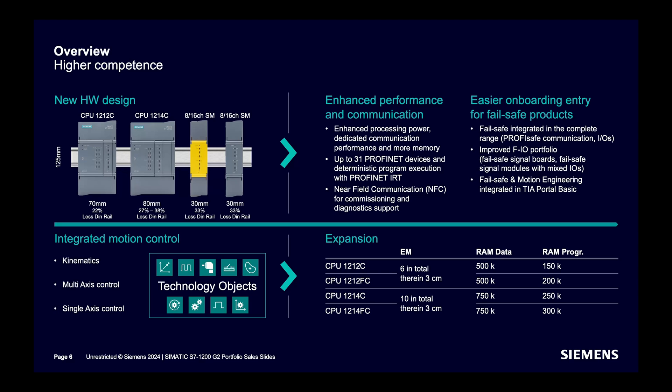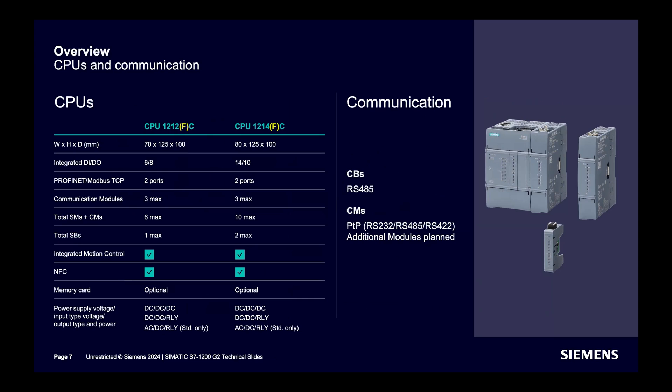This is the overview of the new CPU-1212 and CPU-1214. Width has been reduced and height has been increased. Integrated DI and DO is 6 and 8 for CPU-1212, and 14 and 10 for CPU-1214. Two PROFINET or MODBUS ports are now available. Three communication modules are supported for both. Six signal boards and signal modules are supported for CPU-1212, and ten for CPU-1214. One signal board slot is supported for CPU-1212 and two for CPU-1214. Integrated motion control and NFC are included. Memory card is optional, and different power options are available.